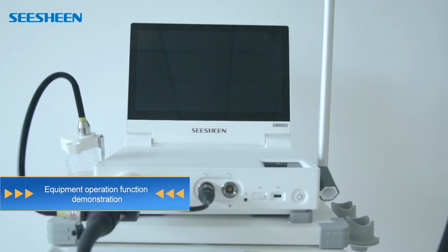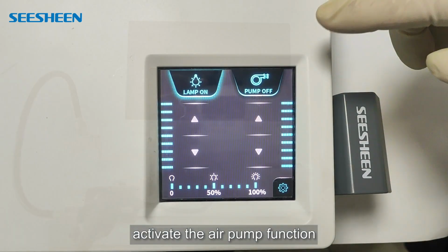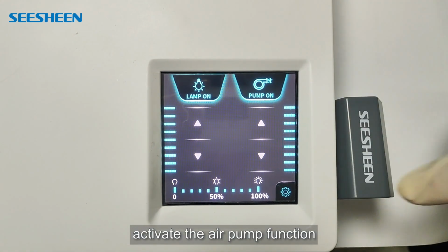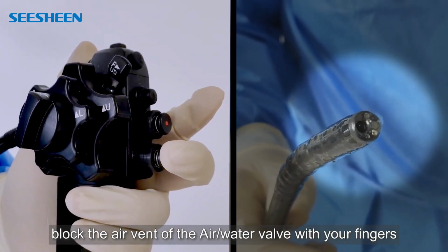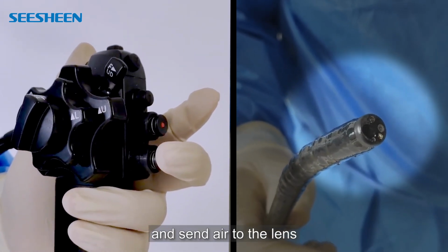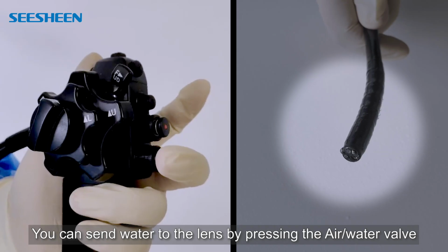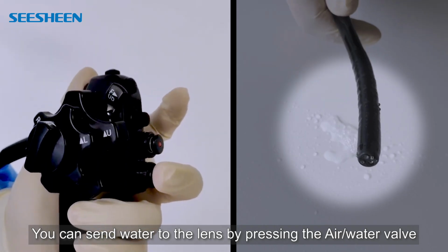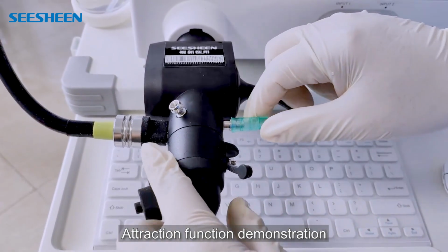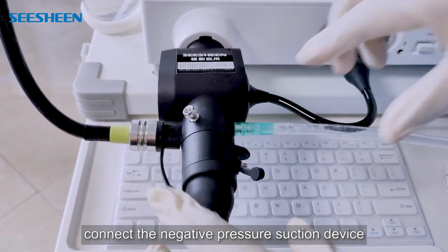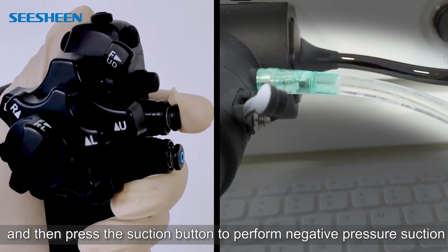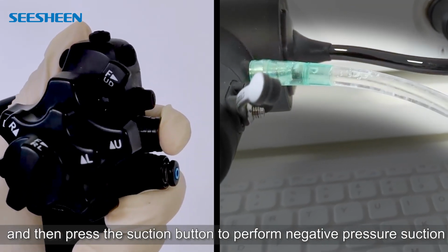Equipment operation function demonstration. Activate the air pump function. Block the air vent of the air/water valve with your fingers and send air to the lens. You can send water to the lens by pressing the air/water valve. Suction function demonstration. Connect the negative pressure suction device, and then press the suction button to perform negative pressure suction.